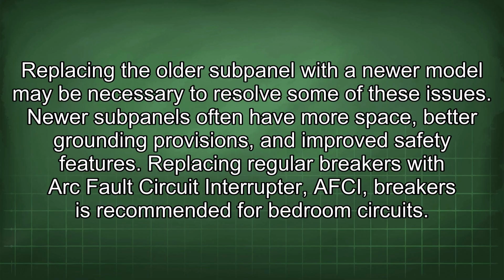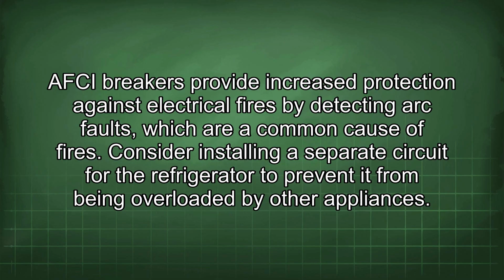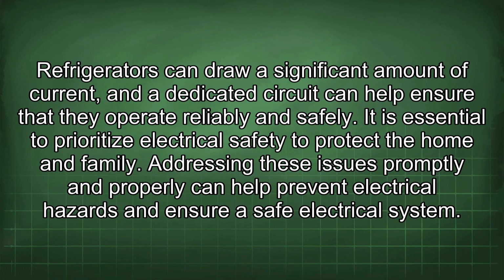Replacing regular breakers with arc fault circuit interrupter (AFCI) breakers is recommended for bedroom circuits. AFCI breakers provide increased protection against electrical fires by detecting arc faults, which are a common cause of fires. Consider installing a separate circuit for the refrigerator to prevent it from being overloaded by other appliances. Refrigerators can draw a significant amount of current, and a dedicated circuit can help ensure that they operate reliably and safely. It is essential to prioritize electrical safety to protect the home and family. Addressing these issues promptly and properly can help prevent electrical hazards and ensure a safe electrical system.